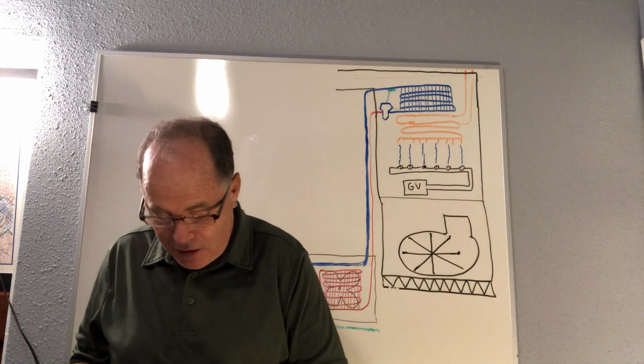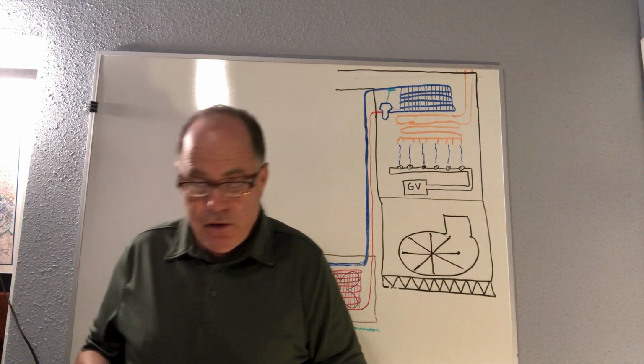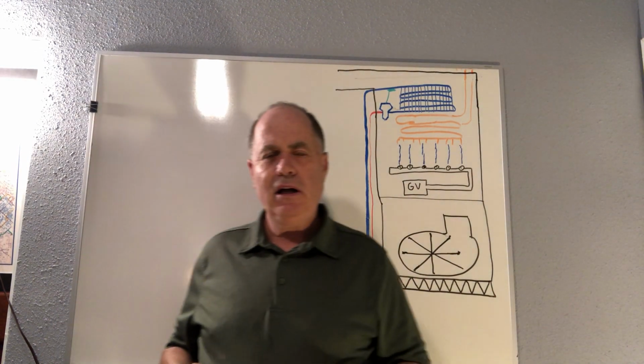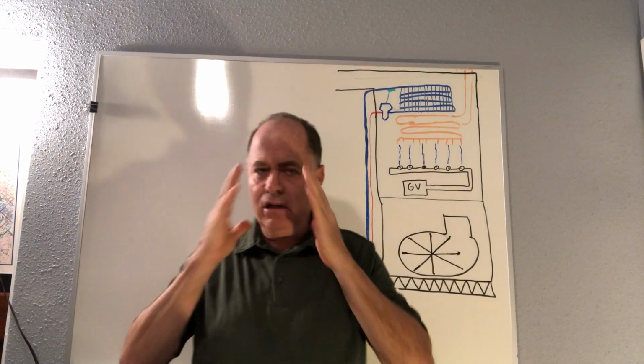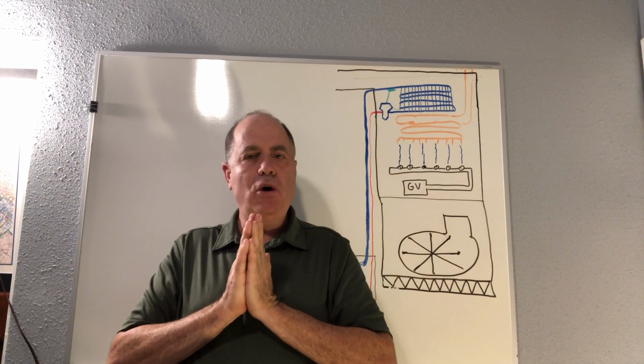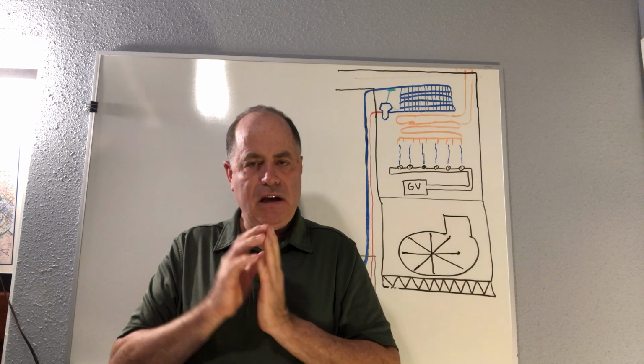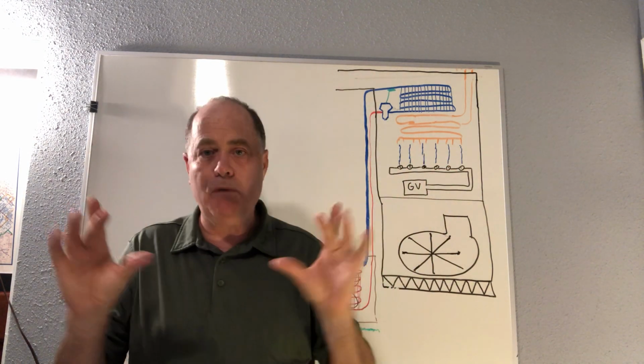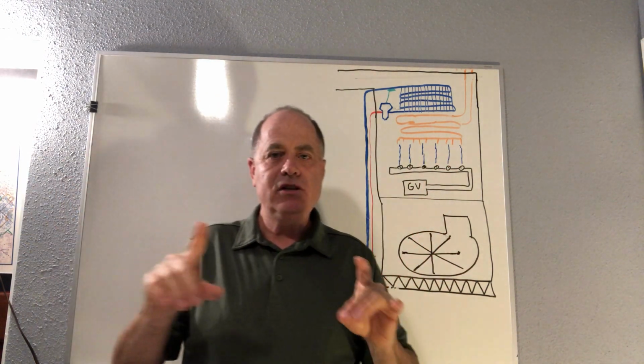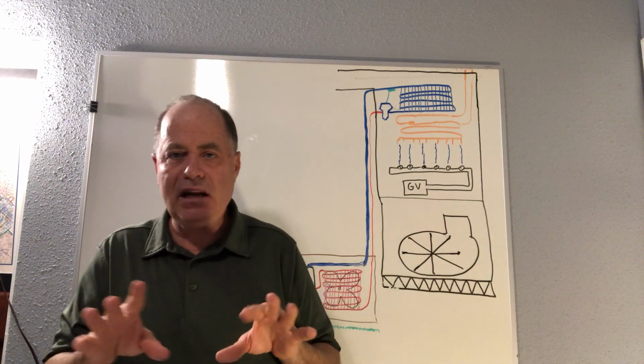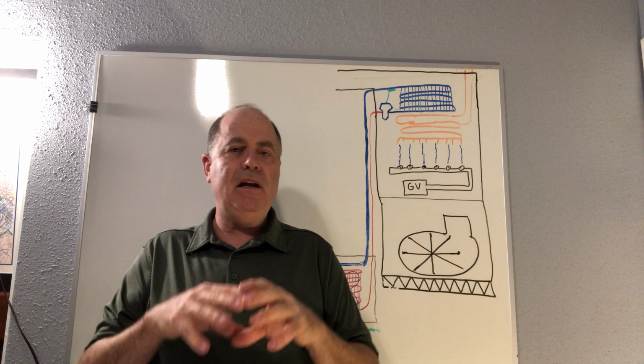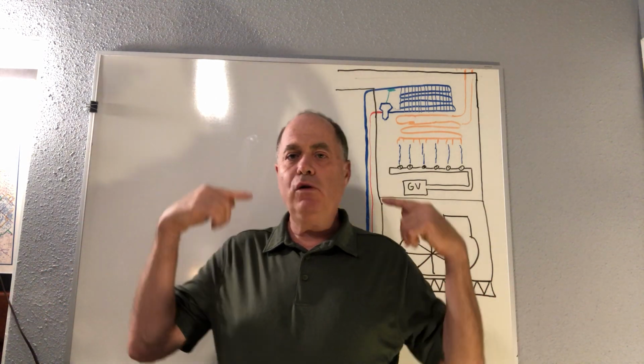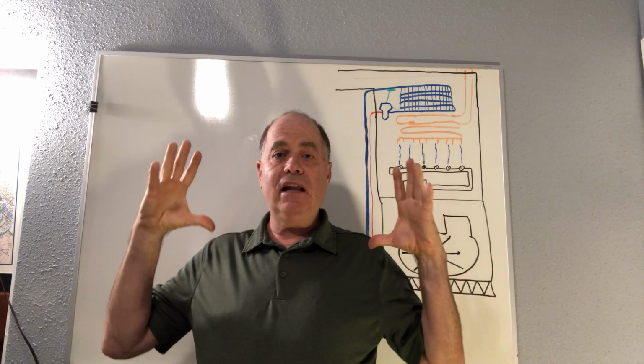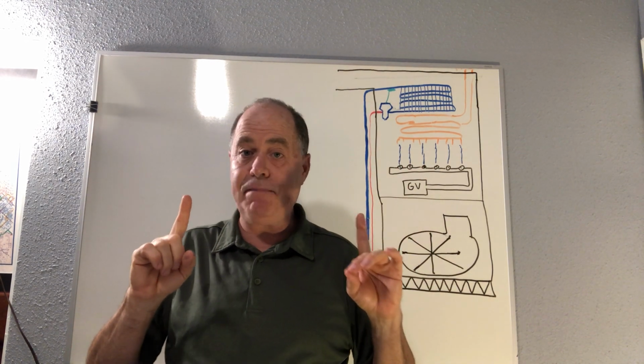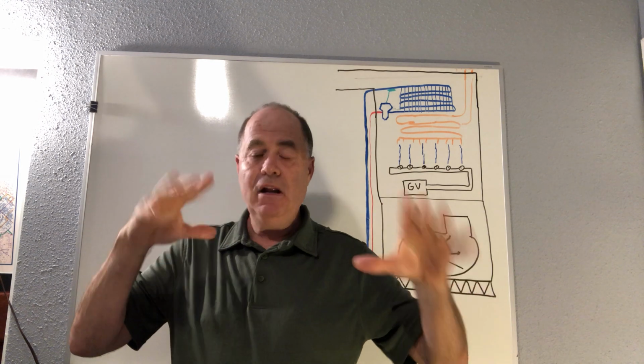Now, there is something called an industrial heater. And I've thought a lot about this. This is a little odd. Industrial heaters can be used, and you don't have to vent them outside. Again, a perfect flame, perfect combustion, produces 0 parts per million carbon monoxide. So not in a residential setting, not in a setting where anyone can sit down and go to sleep, but in an area where people are up and working. They won't let you recirculate that air, but they'll allow you to bring in 100% fresh air. It can't be recirculated where anything can build up. You've got to be taking 100.